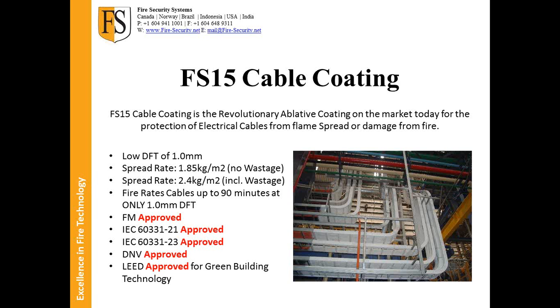Understood. So, to some of the technicalities of our FS15 cable coat, we're very happy with our extremely low dry film thickness. DFT is dry film thickness of 1 millimeter. We do have an FM thickness of 1.6 millimeters, but like all FM products, regardless of what they are, where they come from, or how they're made, FM only tests any type of cable coat at 1.6 millimeters. They do not award you for being technologically advanced. They simply test at 1.6. Our 1 millimeter DFT is for our IEC approvals, 331-21 and -23, which is for the fire protection of electrical cables, not just the spread of flame. It's also for our 90-minute fire rating.